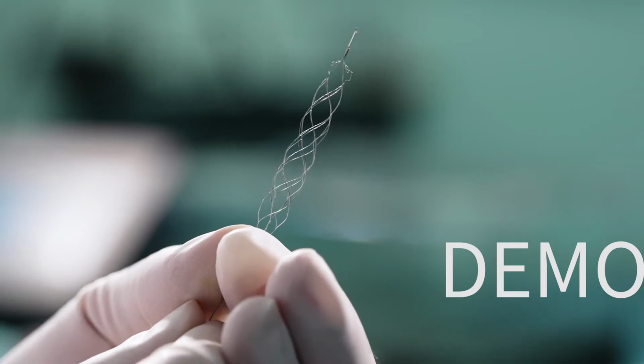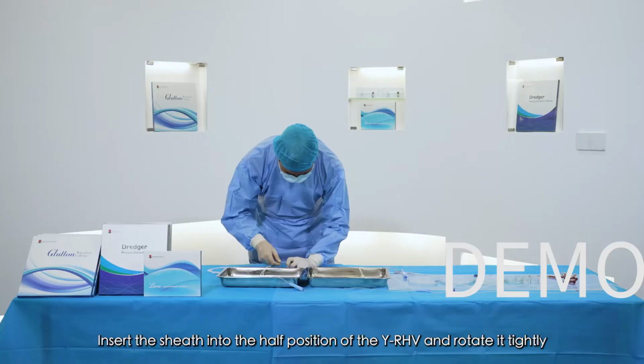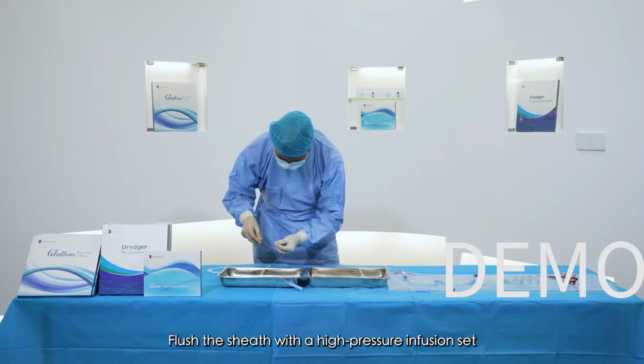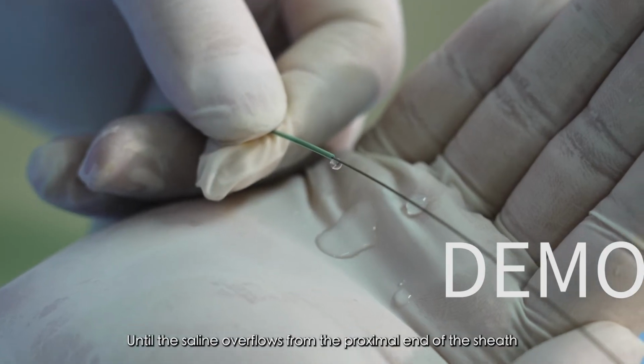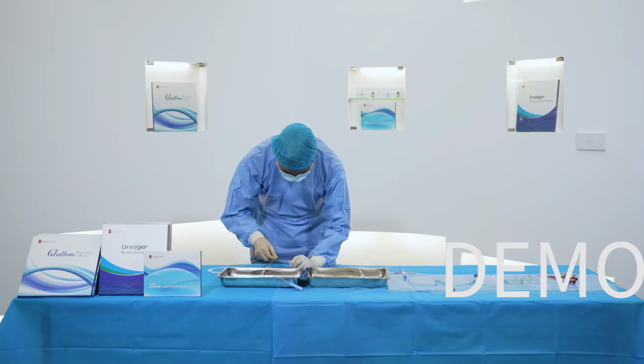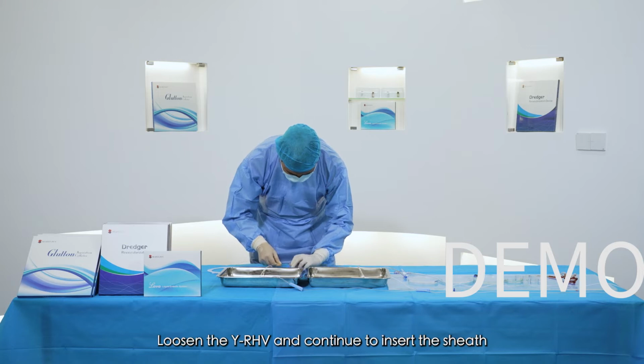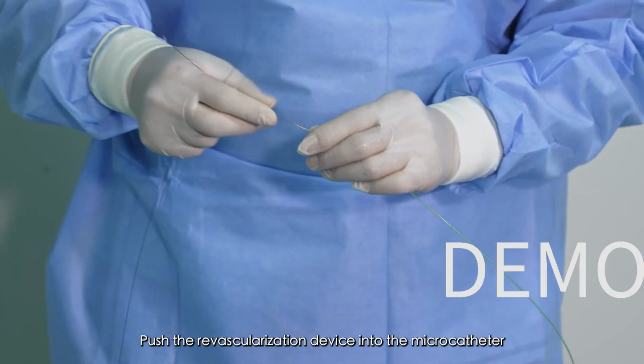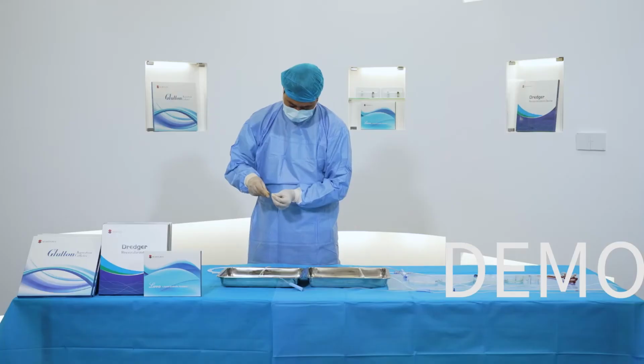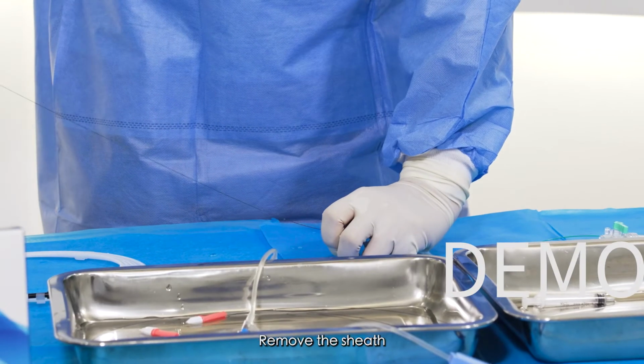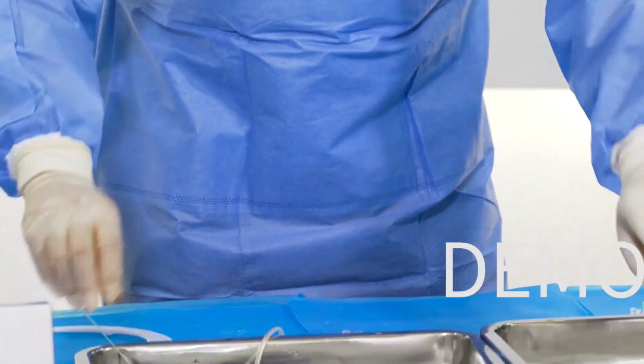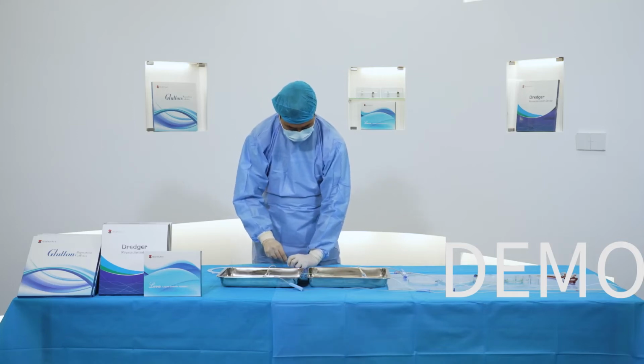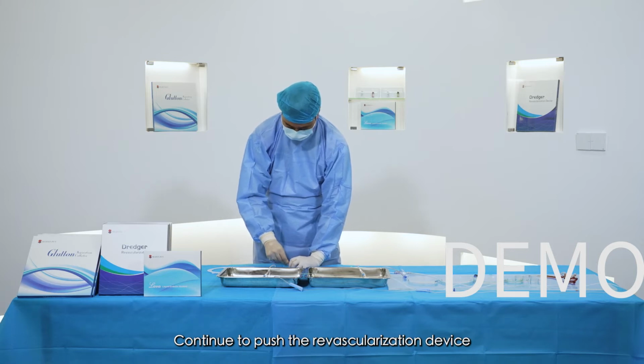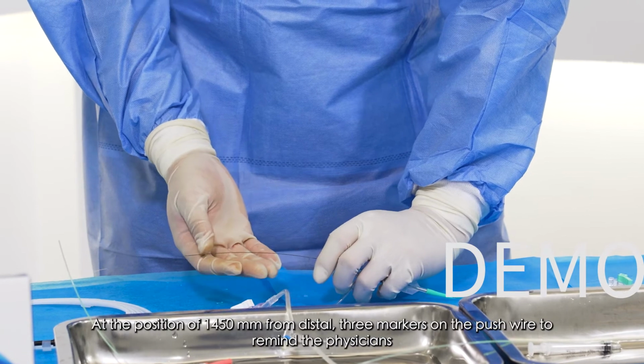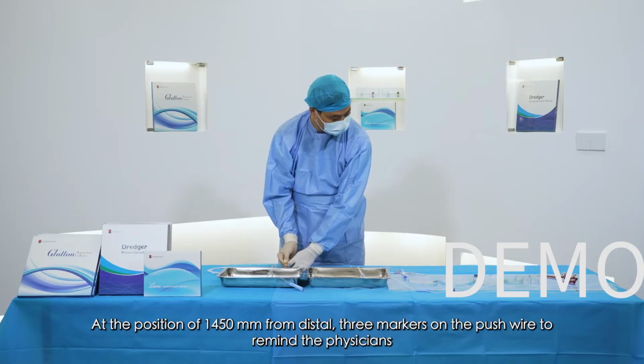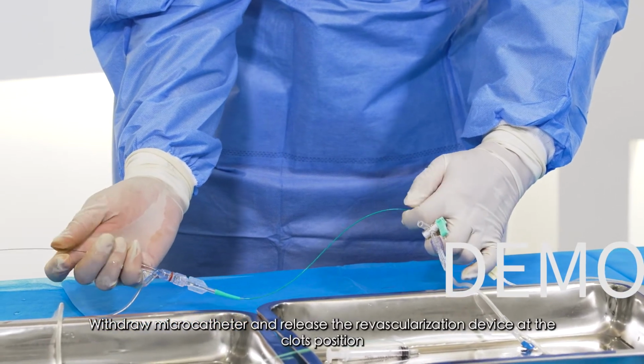Insert the sheath into the half position of the YRHV and rotate it tightly. Flush the sheath with a high-pressure infusion set until the saline overflows from the proximal end of the sheath. Loosen the YRHV and continue to insert the sheath. Push the revascularization device into the microcatheter. Remove the sheath. Continue to push the revascularization device to the position of 1,450 millimeters from the distal end. Three markers on the push wire remind physicians. Withdraw the microcatheter and release the revascularization device at the clot's position.